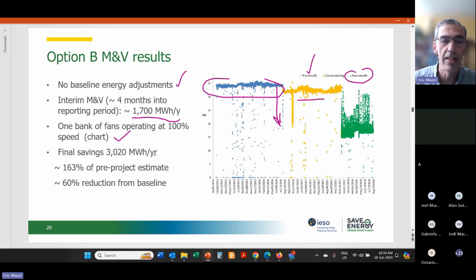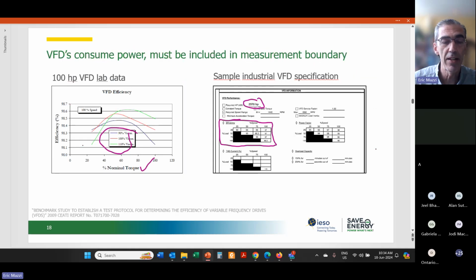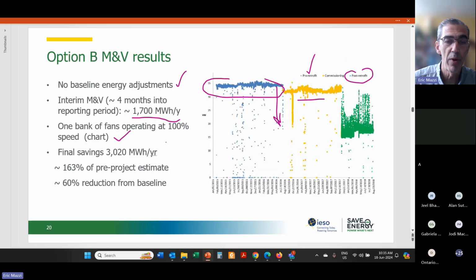An important event from this case study is that based on the interim M&V, an investigation was done into why the savings were not coming out as expected, based on the estimate partway through the reporting period. It was found that there were several fans, maybe 8 or 10, that had the VFD installed but didn't get programmed to modulate. They were running at 100% speed, which meant they were consuming more power than the baseline, because, again, VFDs consume power themselves. If you take a system running at constant speed and add a VFD and just run it at 100% speed, you're going to consume more than your baseline, because you're not only consuming the baseline motor power, you're adding the consumption of the VFD itself. That is what was happening in this project.